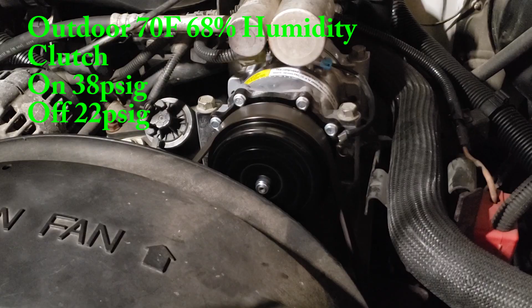Then we're going to hit 22 psig and the clutch will shut off again. Now we're going to take a look at the gauges again. Yep, that is way too short a cycle. It's creeping up from 22 to 38 really fast.